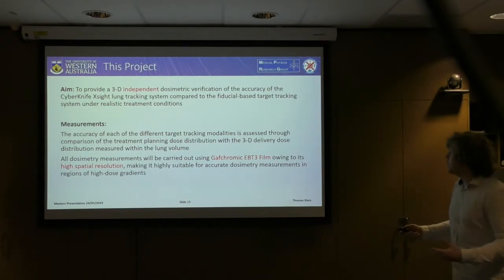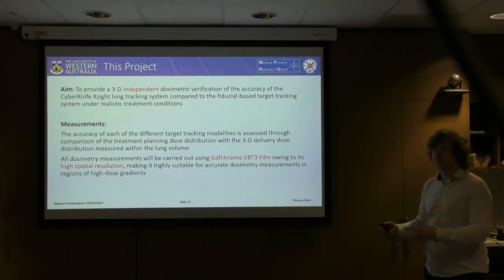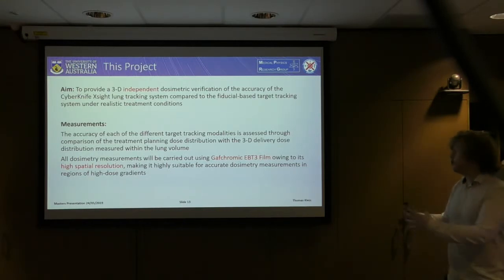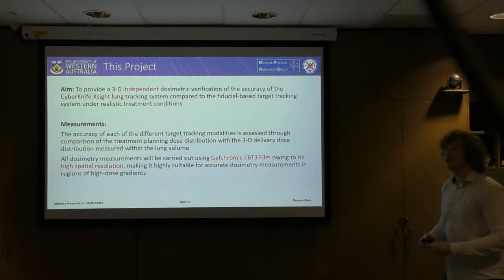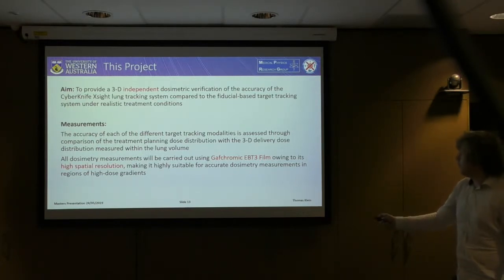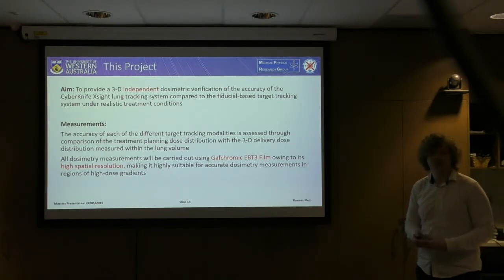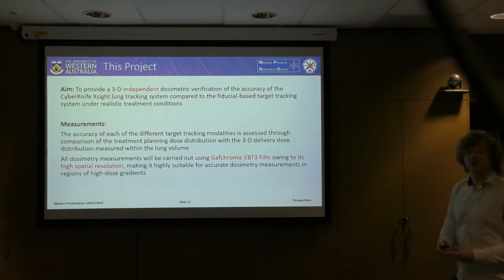To achieve this, we aimed to compare the measured three-dimensional delivery dose distribution within the lung volume to the treatment planning dose distribution. All dosimetry measurements were carried out using gafchromic film, due to its very high spatial resolution, making it highly suited for accurate dosimetry in regions of high dose gradient, which is characteristic of CyberKnife-based treatments.